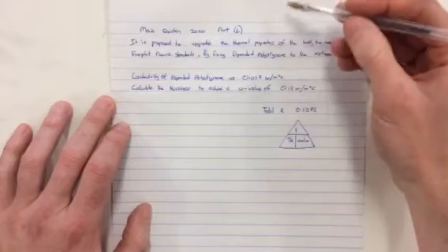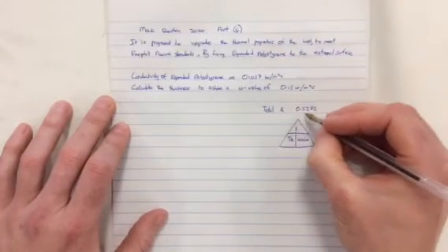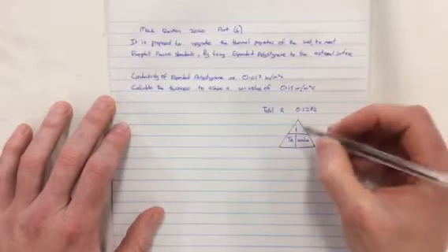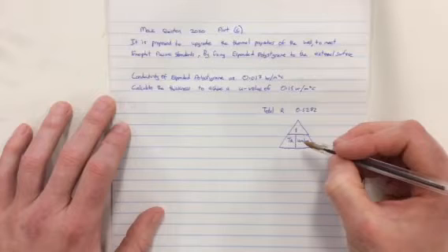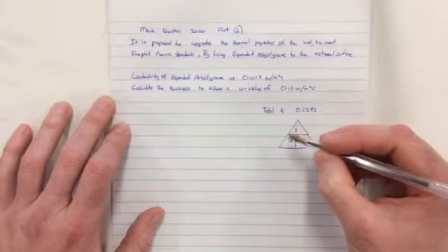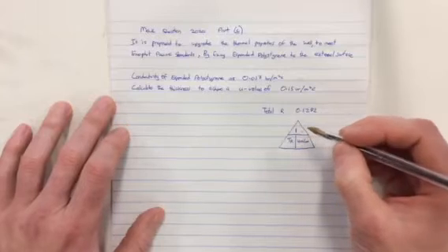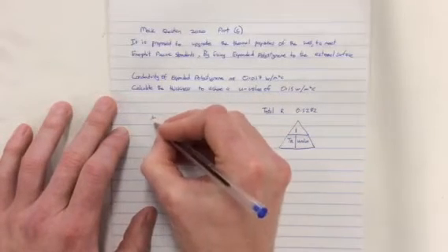So when you have your table done, your total resistance on this question was 0.5282. Then you would go to your formula, so 1 over the total resistance gives you your U value. That's the way you would normally work, so that's what we're going to do here.